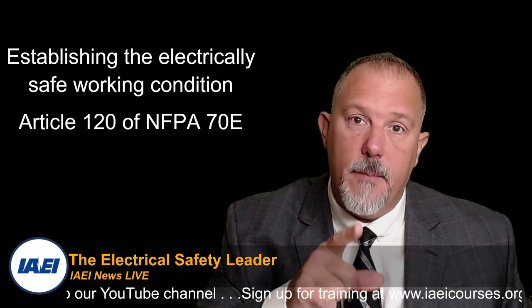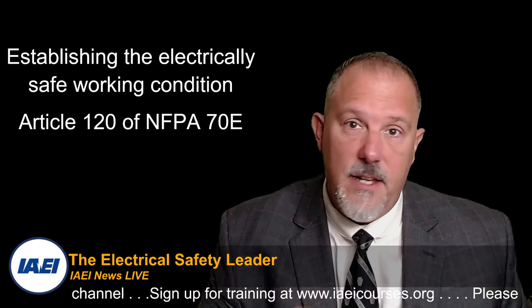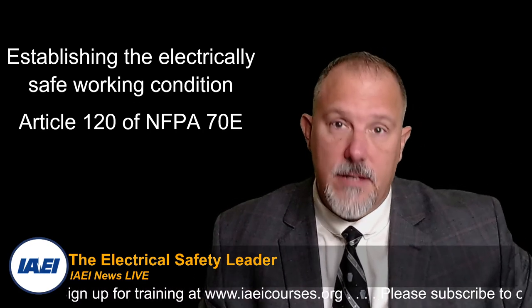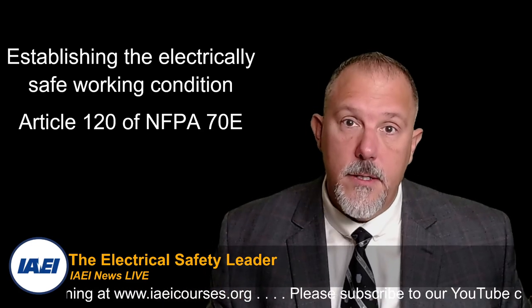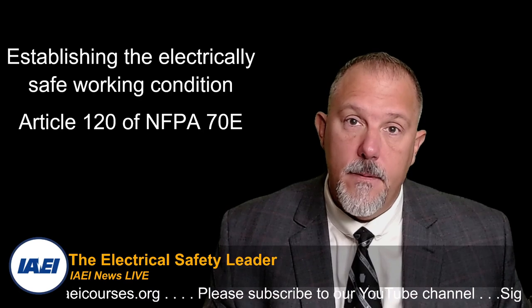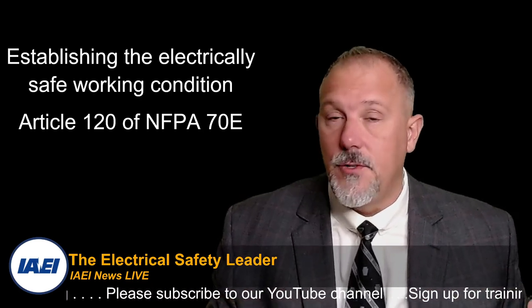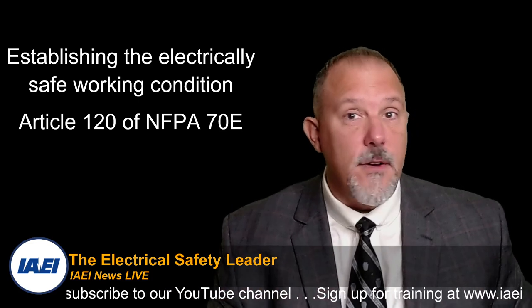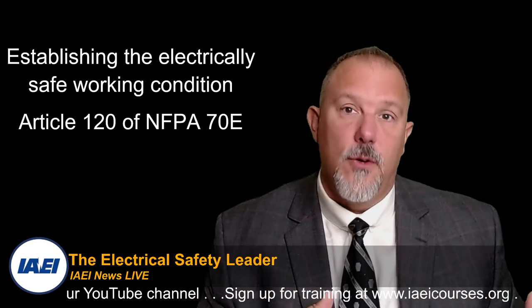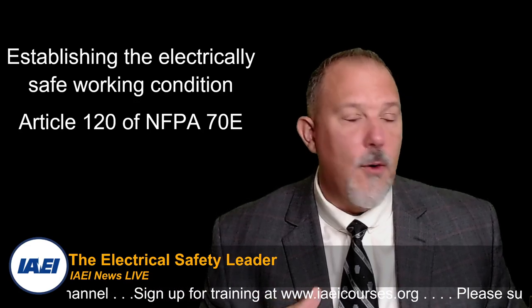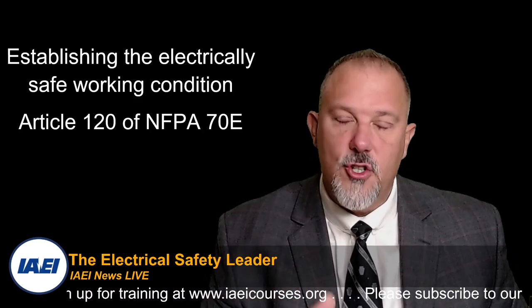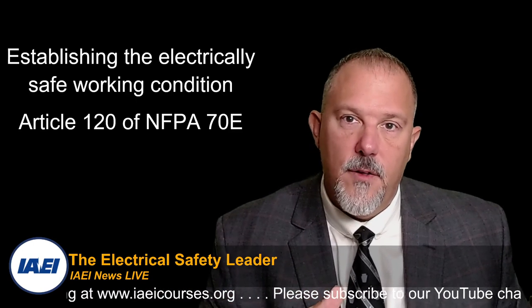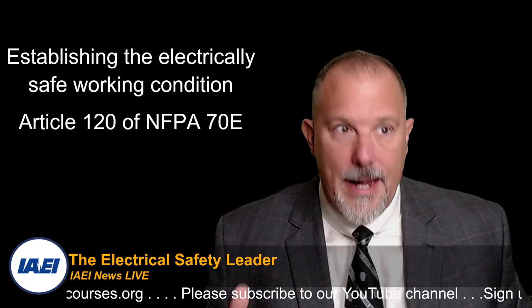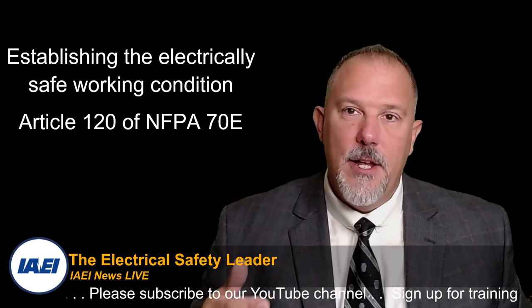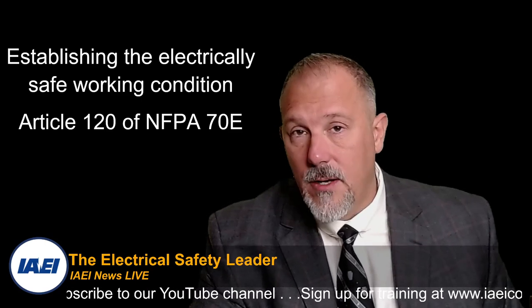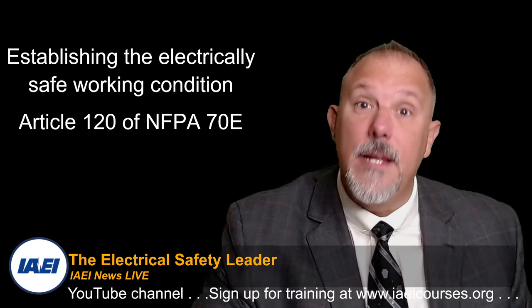But your lockout, tagout policy and procedure may drastically differ from someone else's lockout, tagout procedures. Why? Because you have different equipment. The equipment in your facility helps establish the hazards that you might have in your facility, and that will be different than someone else's. The safe work practices for a residential wireman, a residential electrician, are different than for somebody who works in an industrial facility. The hazards are different. You say, well, Tom, there's arc flash. Is there arc flash? Are there arc flash hazards in a residential dwelling unit?